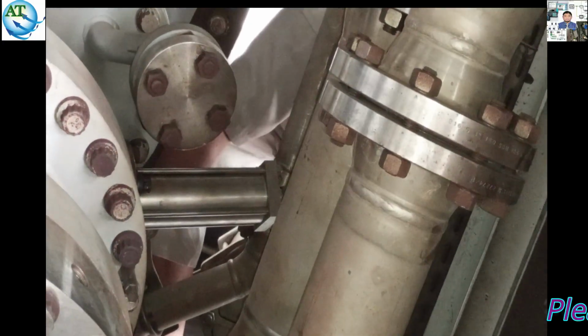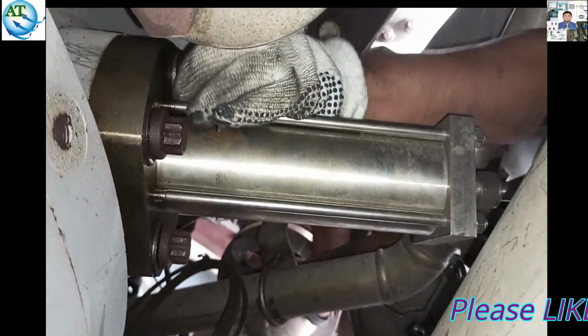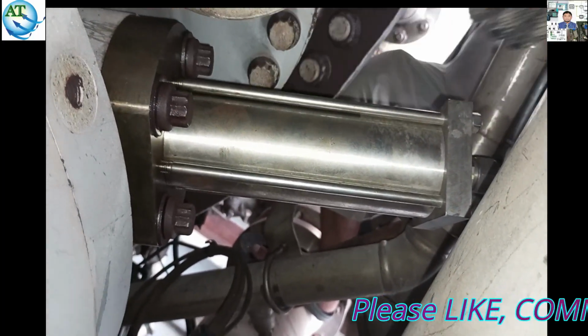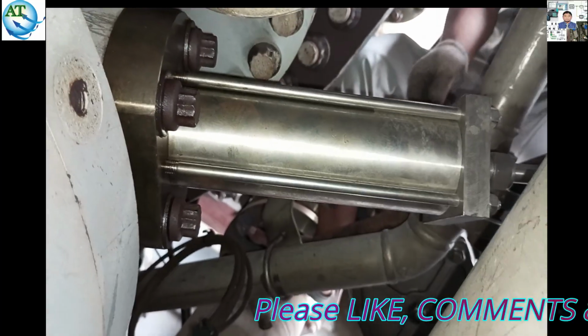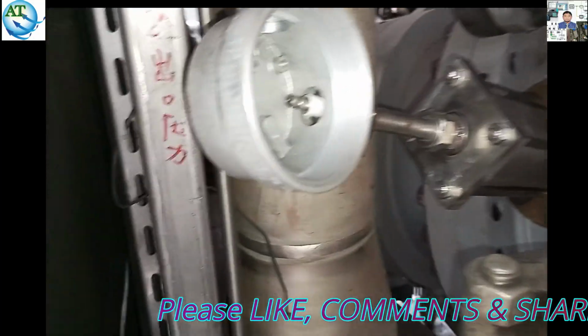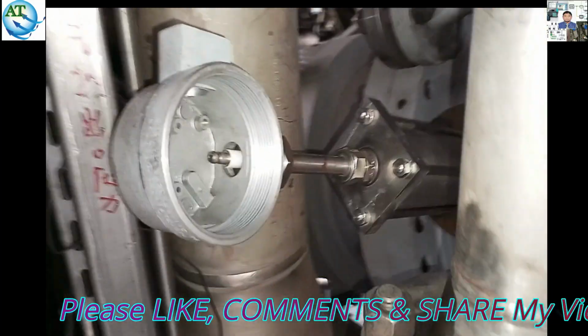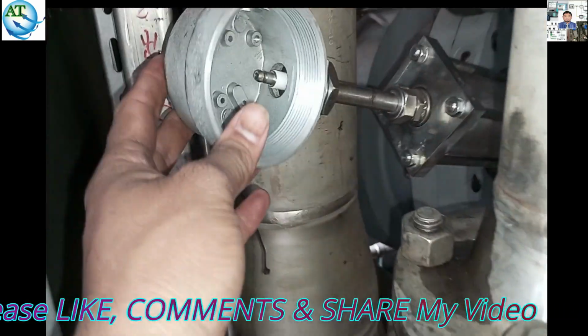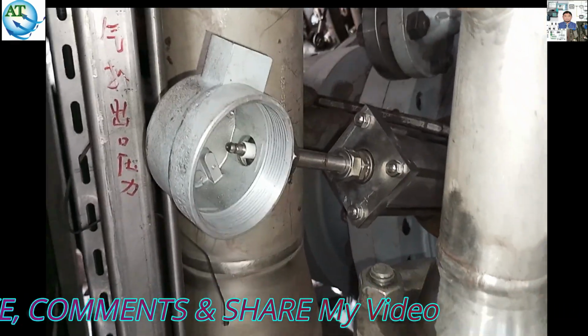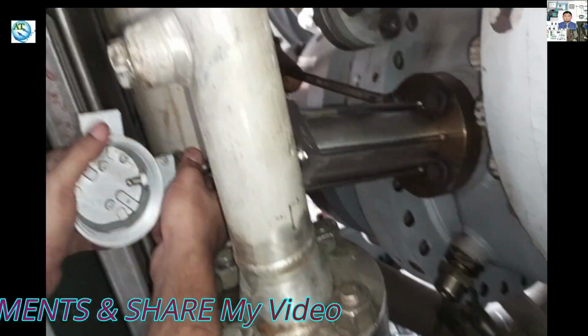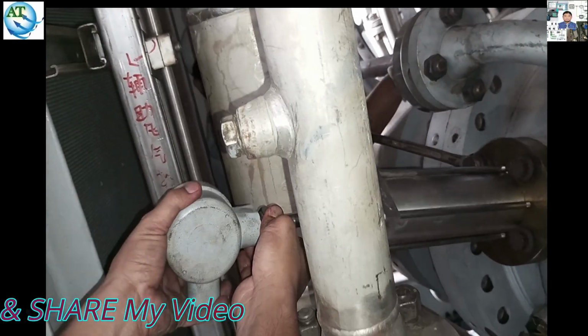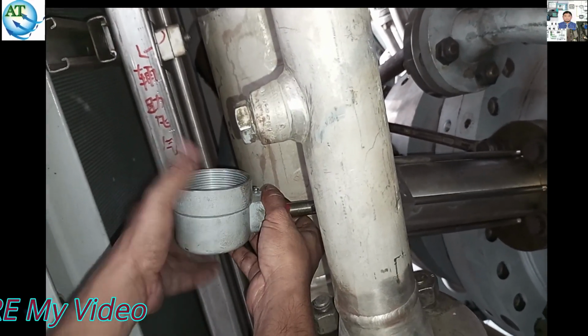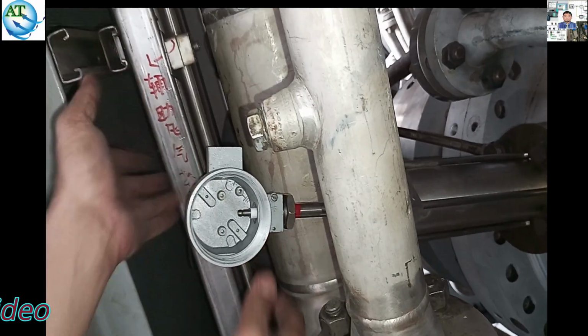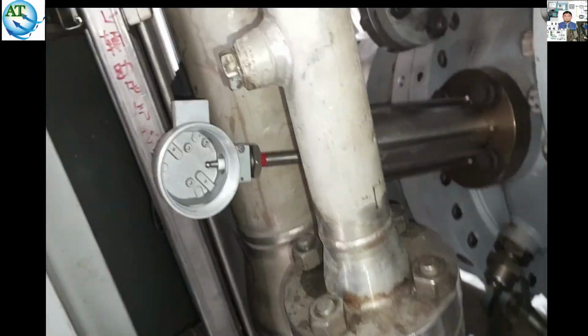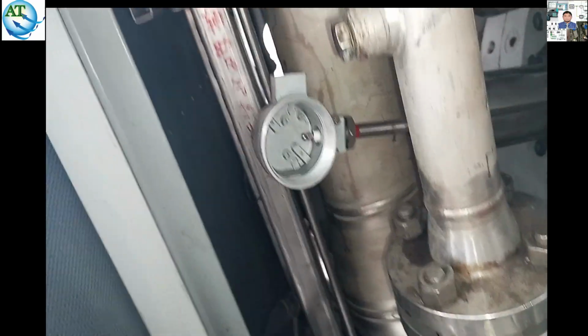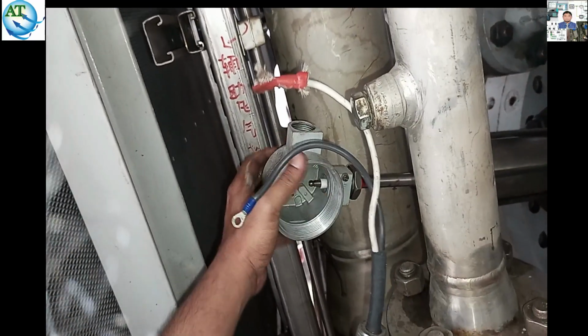We are getting 3.04 mega ohms, but it must be in the ohms range. So we find both are damaged, so we have decided to change both of these igniters. So we have already inserted the new igniter. Now we are connecting this cable. You see, we have already tightened the base nut. Now we are connecting the igniter cable.